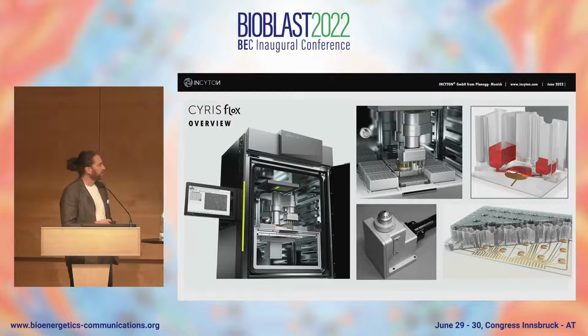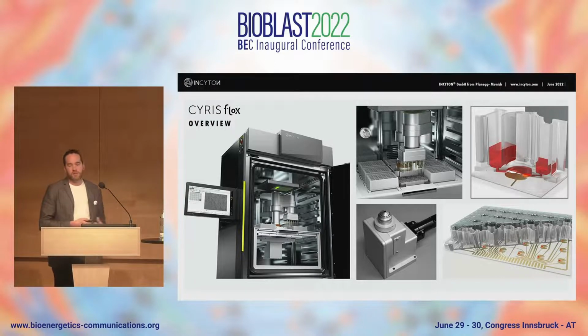This sensor well plate is more or less the core of our measurement system. It has 24 chambers, and each is equipped with a microfluidic channel for media supply, sensors for oxygen, pH, and impedance, and a dedicated window for microscopy. You see here the media inlet, the microfluidic channels, and then the micro-reaction chamber where the cells are added.